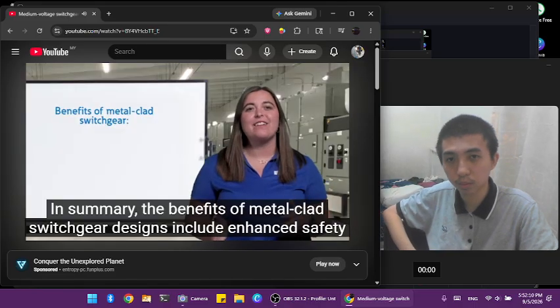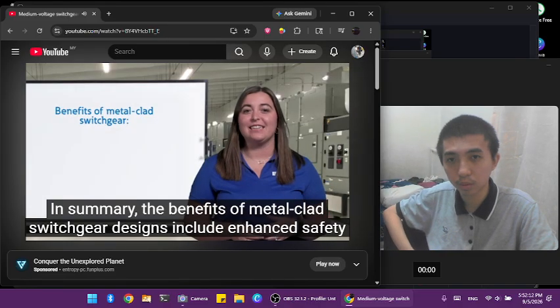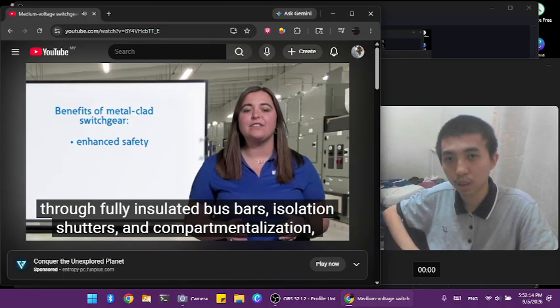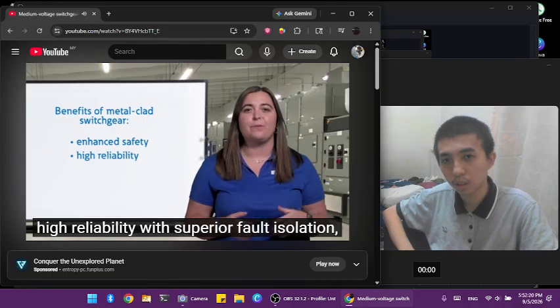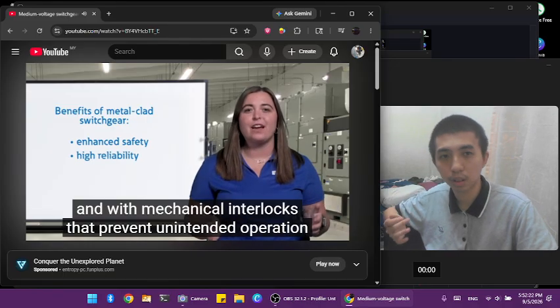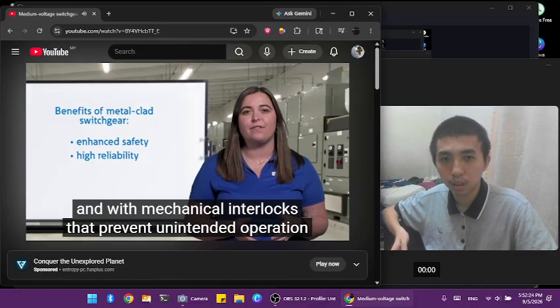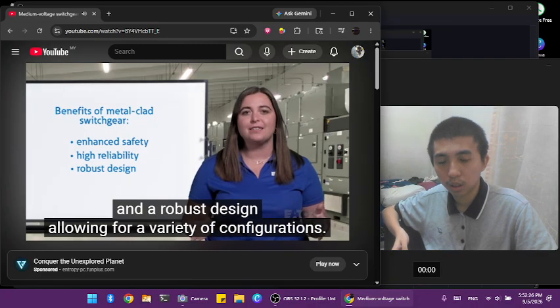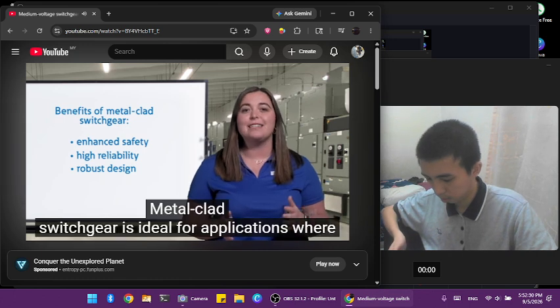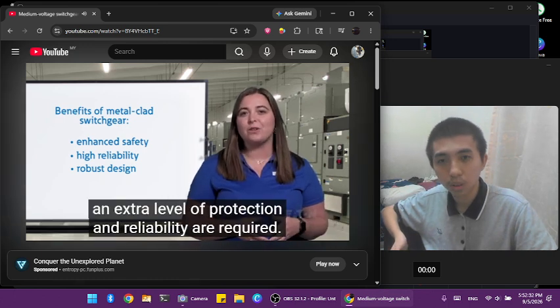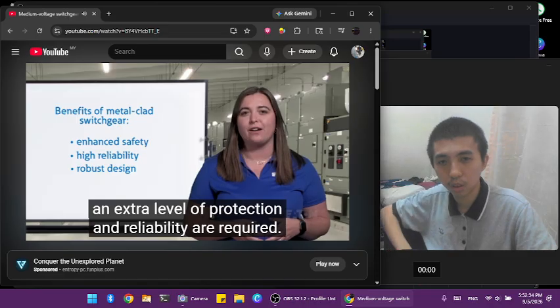In summary, the benefits of metal-clad switchgear designs include enhanced safety through fully insulated bus bars, isolation shutters, and compartmentalization, high reliability with superior fault isolation and with mechanical interlocks that prevent unintended operation, and a robust design allowing for a variety of configurations. Metal-clad switchgear is ideal for applications where an extra level of protection and reliability are required.